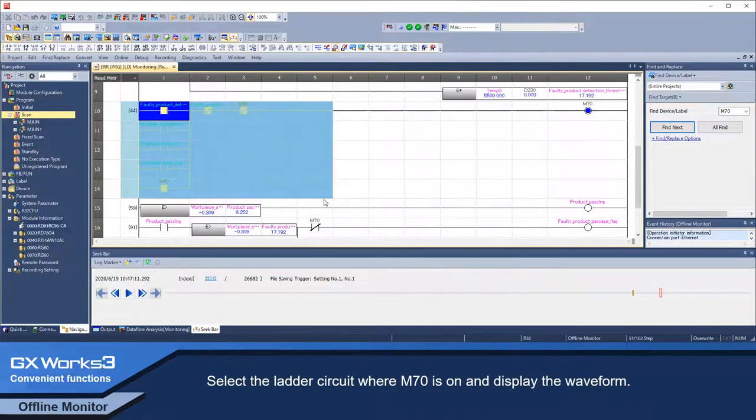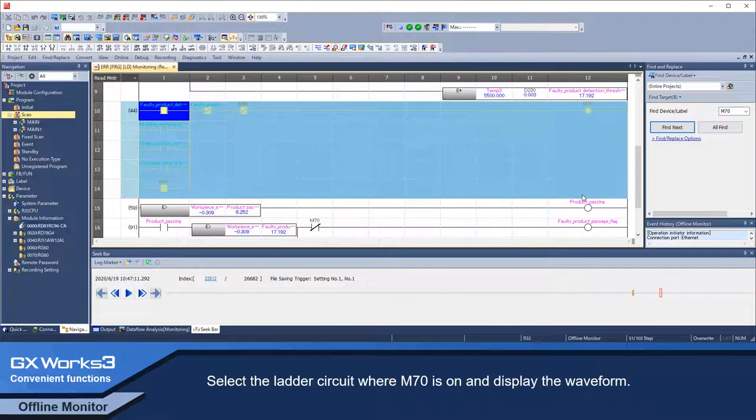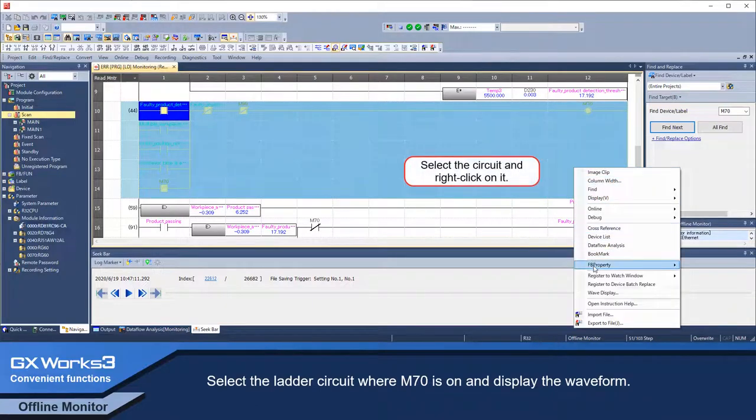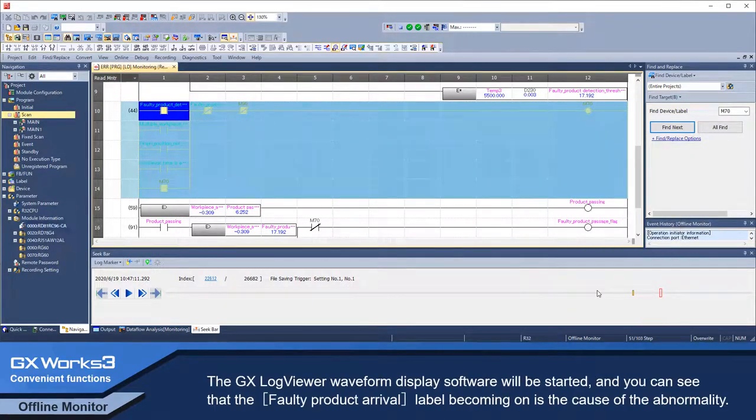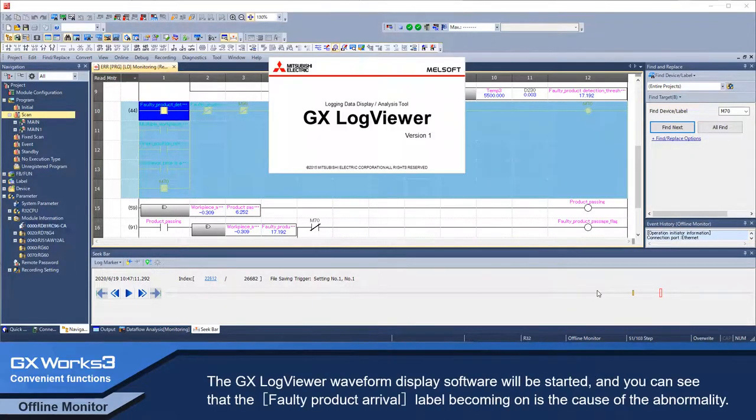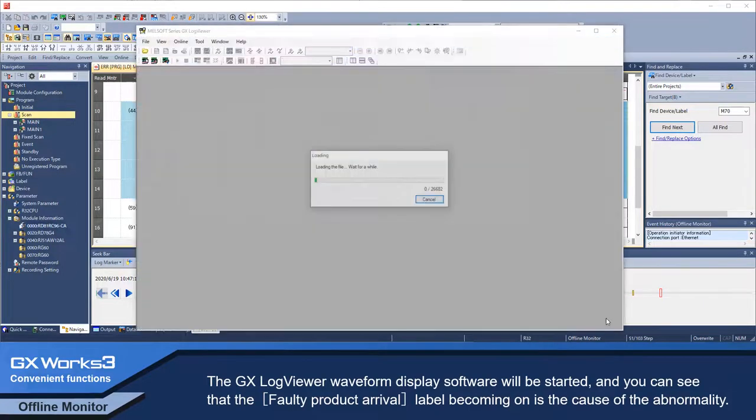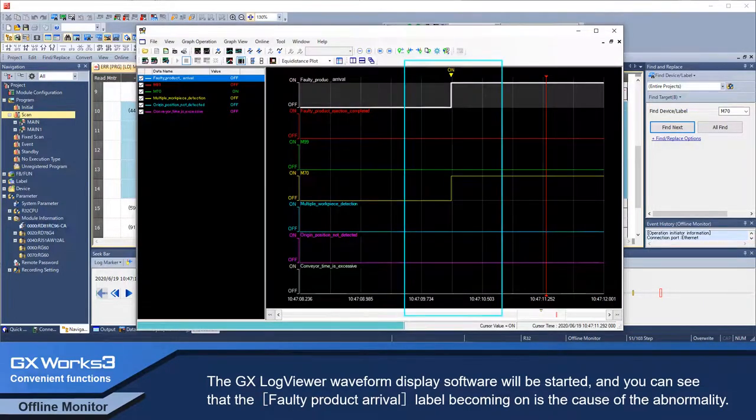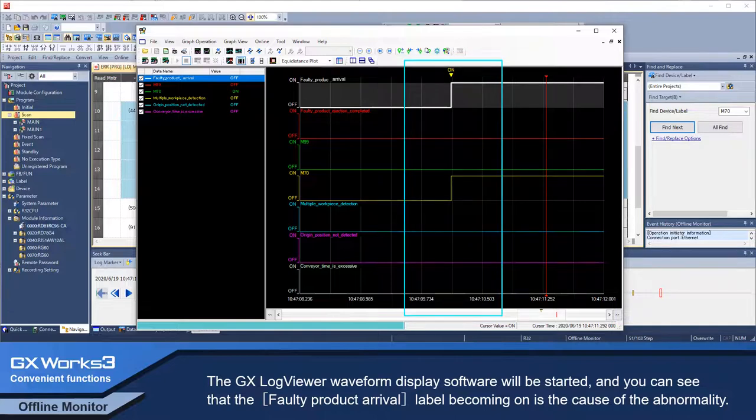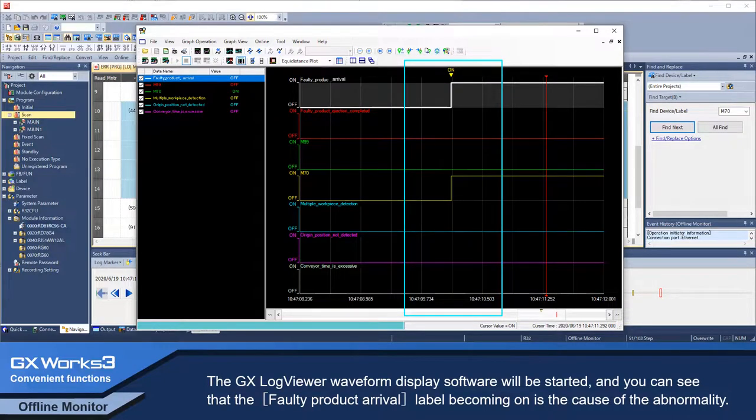Select the ladder circuit where M70 is ON and display the waveform. The GX Log Viewer Waveform Display software will be started and you can see that the faulty product arrival label becoming ON is the cause of the abnormality.